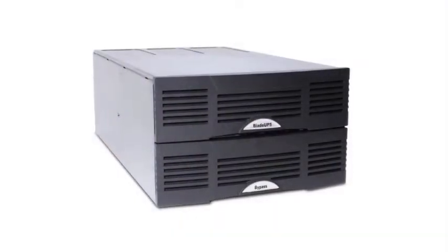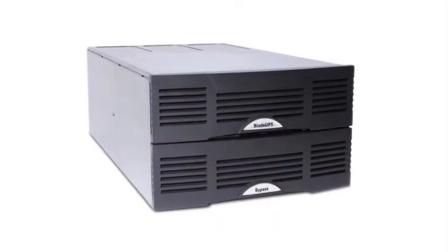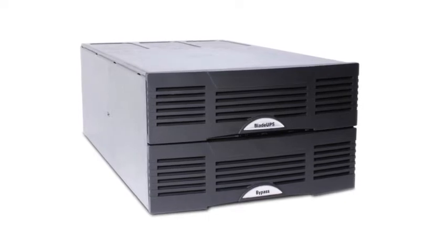We use these maintenance bypass units from Eaton. We're actually just going to put in one of their new units. We're going to test out putting the maintenance bypass inside the BladeUPS cabinet itself to save some room on the wall for our dedicated server room.